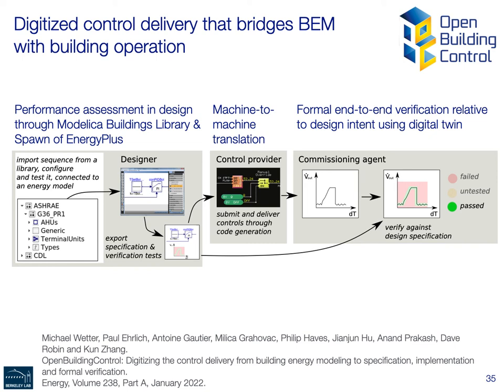This will allow a designer to do performance assessments through the Modelica Buildings Library or Spawn of EnergyPlus, export the control specification in a vendor-independent format, so that a control provider can bid on the job and then translate that to their native implementation using machine-to-machine translation. The commissioning agent will then have the formal specification of the control sequence in the form of a digital twin, and use that to verify that the as-installed control sequences conform to the design specification.